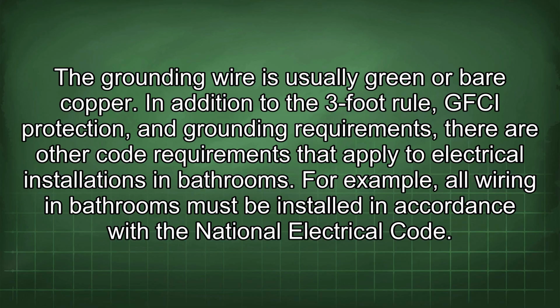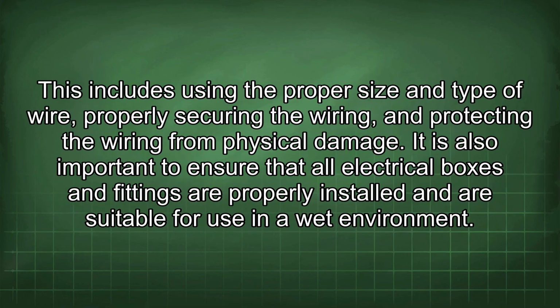In addition to the 3-foot rule, GFCI protection, and grounding requirements, there are other code requirements that apply to electrical installations in bathrooms. For example, all wiring in bathrooms must be installed in accordance with the National Electrical Code. This includes using the proper size and type of wire, properly securing the wiring, and protecting the wiring from physical damage. It is also important to ensure that all electrical boxes and fittings are properly installed and are suitable for use in a wet environment.